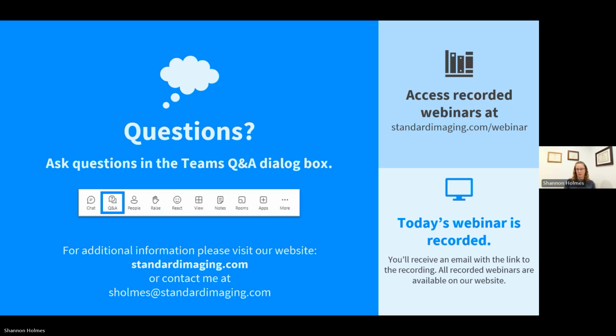And our Max Elite 2-channel or 4-channel Max Elite has a built-in camera with a data matrix reader. So just like scanning a QR code with your phone, you turn the camera on, it will capture that data matrix code, and then it'll automatically pop up a dialog that has the calibration information filled in for that chamber, and you can confirm it. If it's one that's been entered already, it recognizes it's a duplicate. It'll inform you of that. And you can then track your calibrations under that same serial number chamber within the electrometer itself, and have those available for if you want to do the dose conversion.